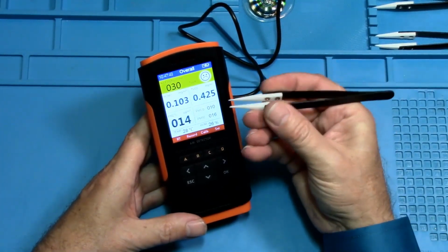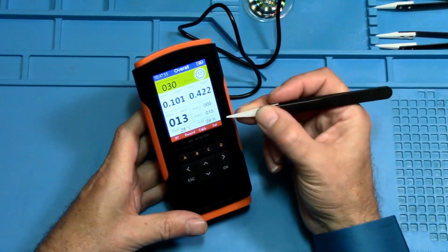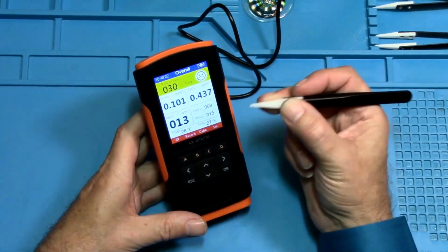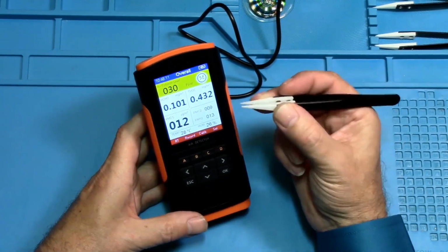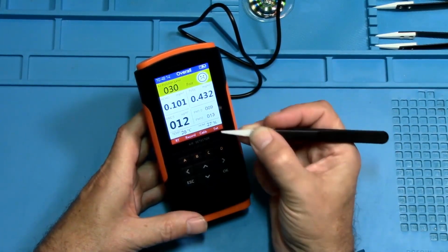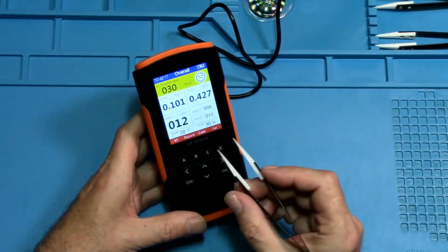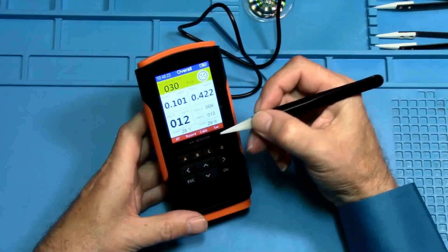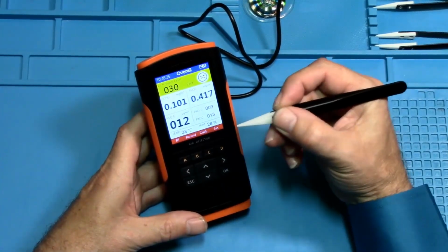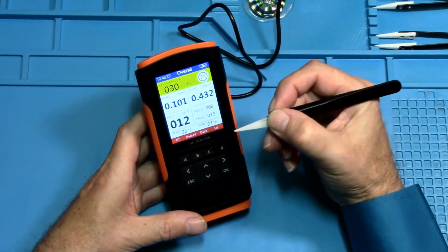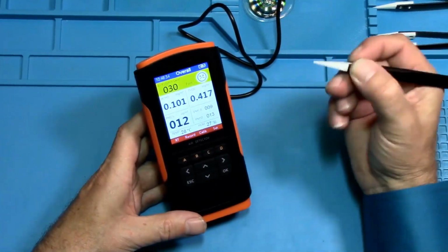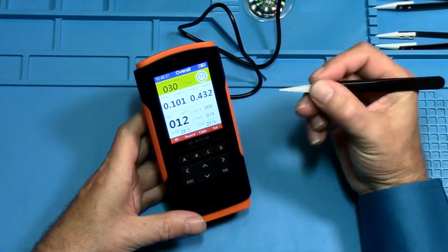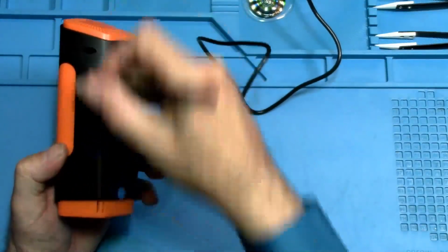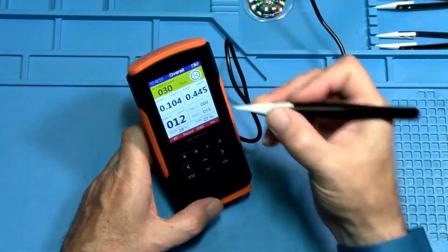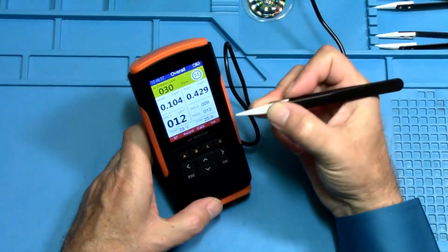So what I recommend to anybody is to take them out of the packaging when you first buy them. Leave them off and put them in fresh air for a day or half a day, 3 or 4 hours. Then go through the calibration of each unit that it specifies. Now, some won't say that it needs to be calibrated in the manual, but you can do a self-calibration. That self-calibration is just to leave it in fresh air that you know to be fresh, and just leave it there. Go to the store, go out, whatever you've got to do. Leave it there, if you can, for a day. Just leave it out in the fresh air for a day so oxygen can get in through all of this and kind of clean it. But then if the manual says it has a calibration function, then follow the calibration procedure in the manual after that.